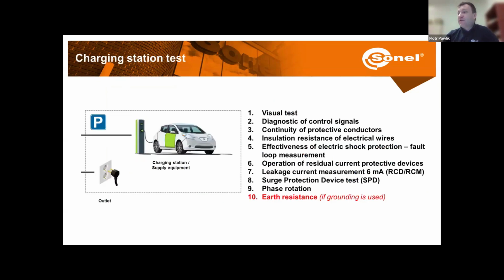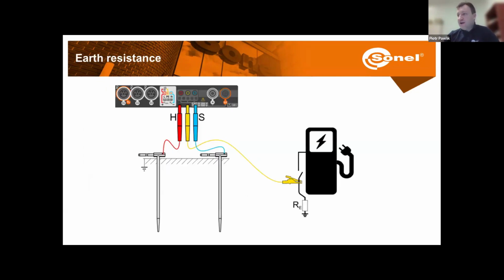And the final test, this is only for the charging stations which have some earthing of their own. We need to check its earth resistance. So, for example, here I'm showing the three-pole method. So we need to disconnect the earthing from the charging station and create the measuring circuits using two rods to the earth. Further one, this is the current rod.